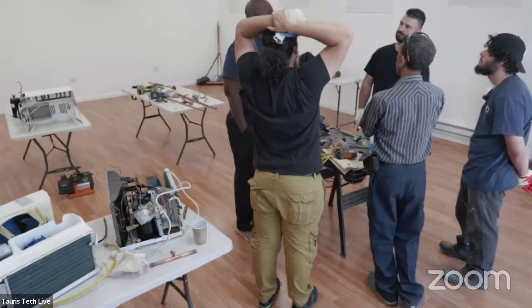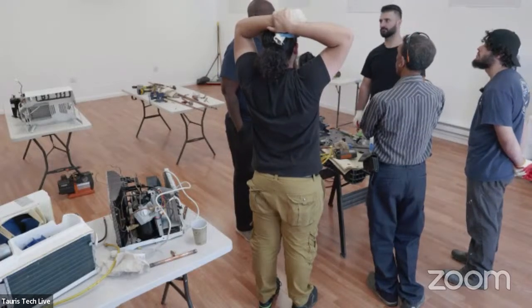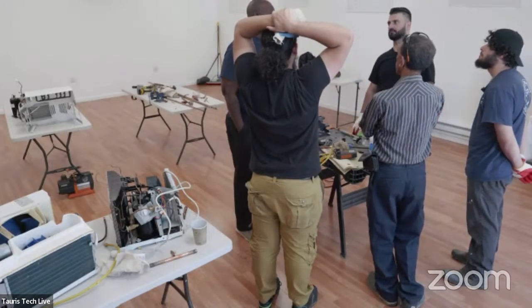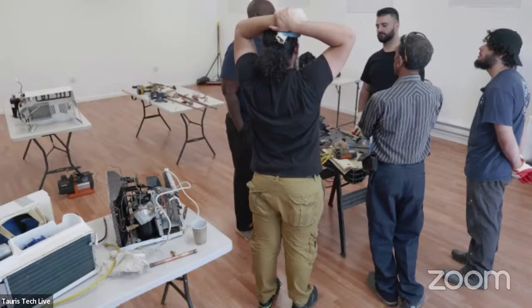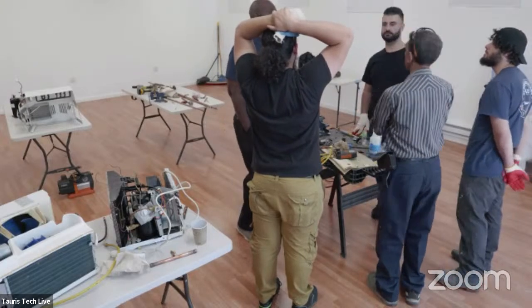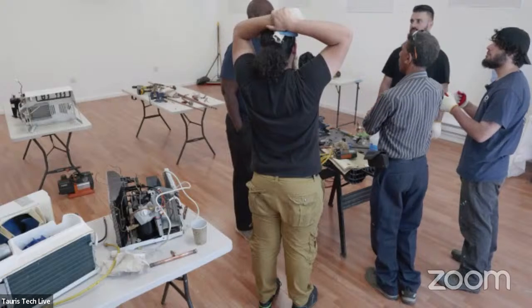If you got a leak and it's stuck in the air, it won't go past 0 PSI, it'll stay at atmospheric pressure. So that's why you have to wait with the vacuum, because it has to pull out the moisture. It boils up the moisture, it's there.